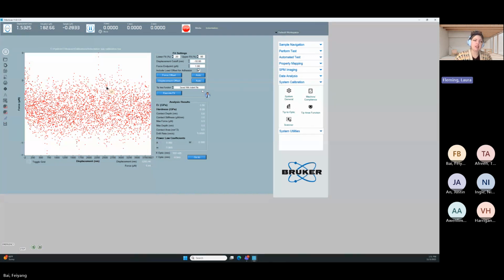Okay. Yeah, there's nothing wrong with this air indent. I was just being curious. It has about a 1 micronewton spread. And sometimes on quieter systems, what we see is like a smiley face because we can actually see the actuation out and the actuation back, and there's some small hysteresis. Here, the noise is high enough that it covers that up and averages it out, so we can't see that differentiation. But that's no problem. So, yeah, this looks great for the system.